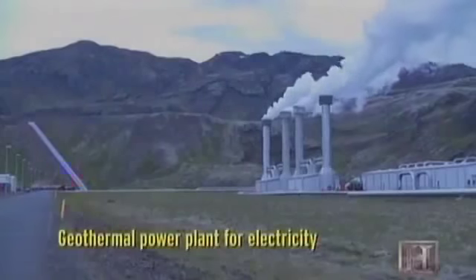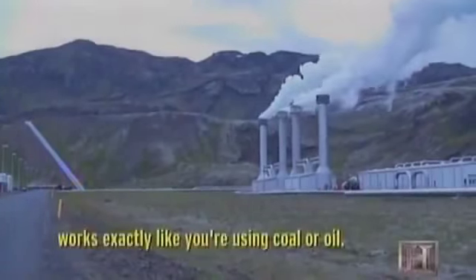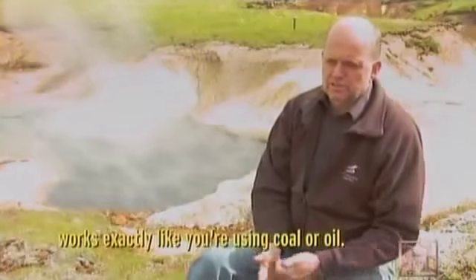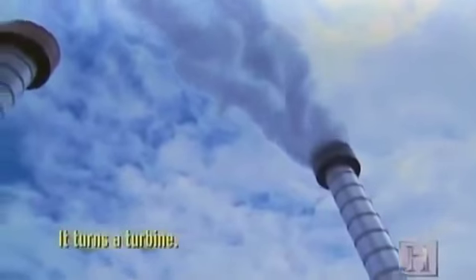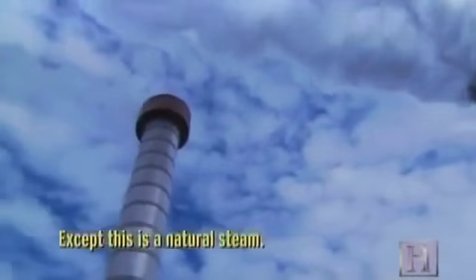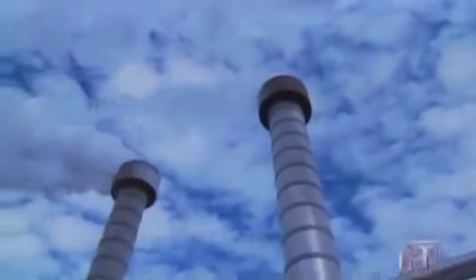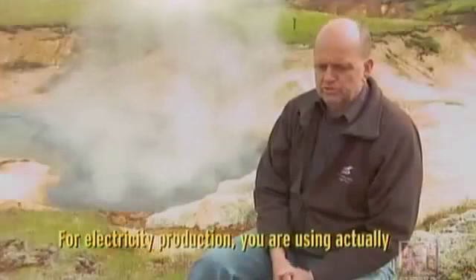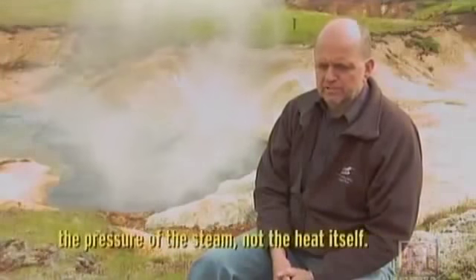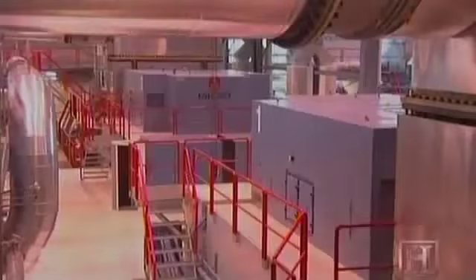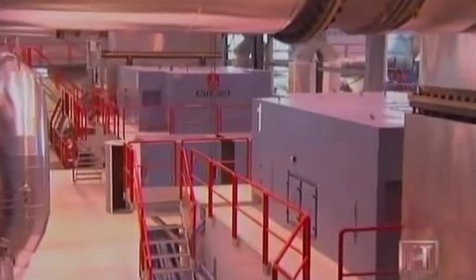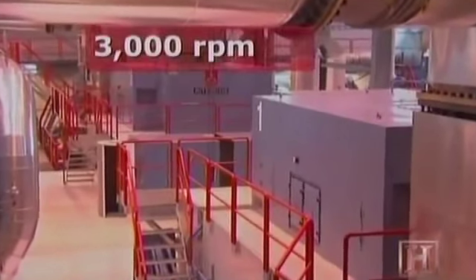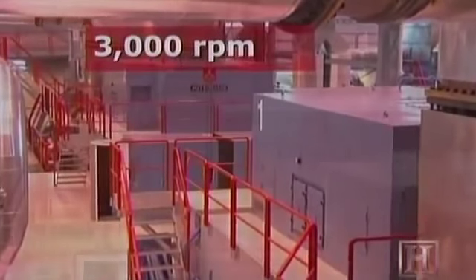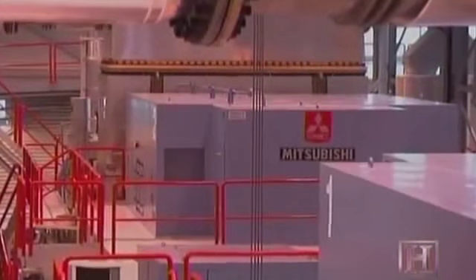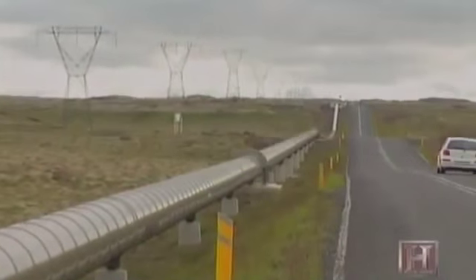A geothermal power plant for electricity works exactly like using coal or oil in terms of the turbine, except this is a natural steam. For electricity production, you're actually using the pressure of the steam, not the heat itself. The steam turns one of 4 turbines at a rate of 3,000 RPM. The turbines combine to generate 120 megawatts of electricity, which is sent on to Reykjavik.